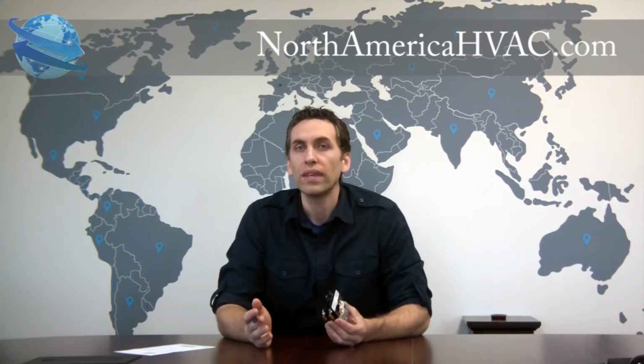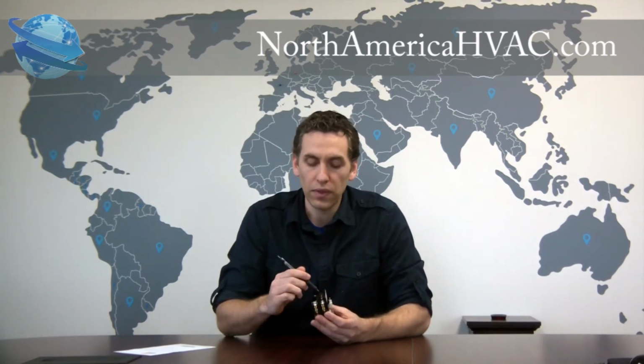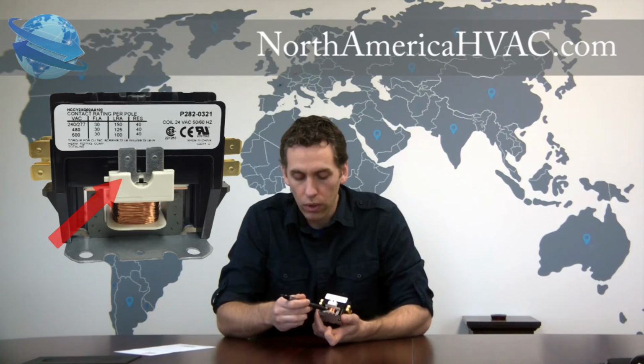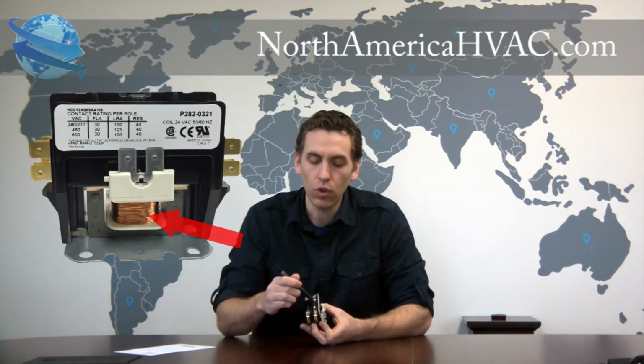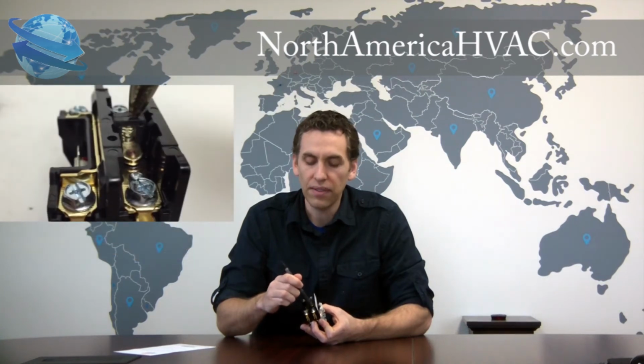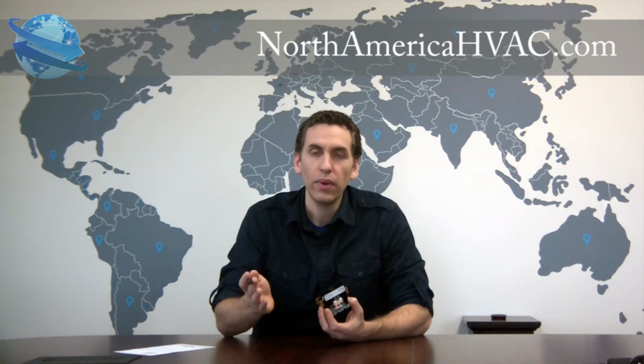The coil voltage is usually a lot less than the load voltage, and you're going to attach your coil wires here on this side. And what happens is the coil voltage runs through a coil down here at the bottom, creating a magnetic field which causes this button to be pushed down, creating the connection that we need between the bottom and the top.